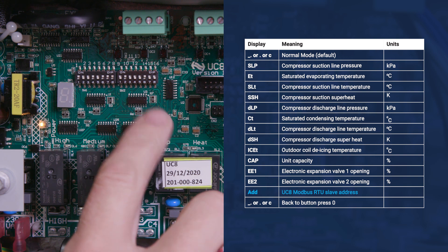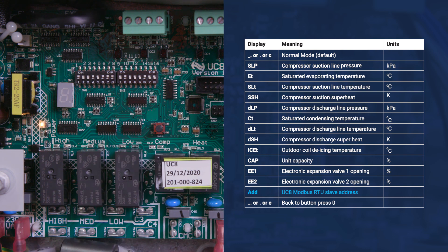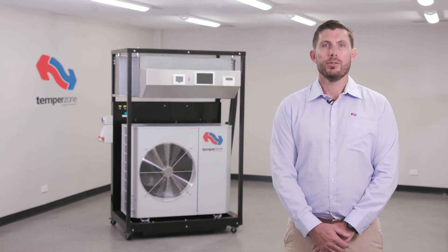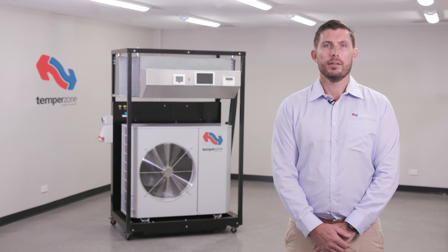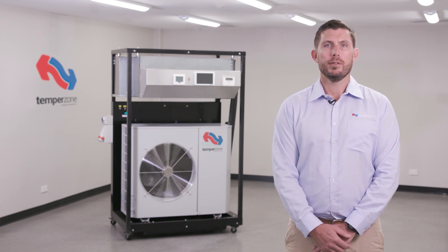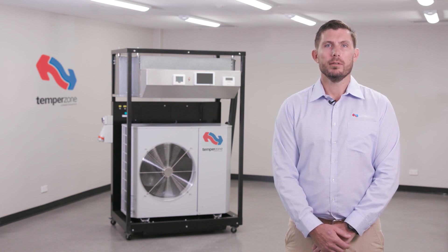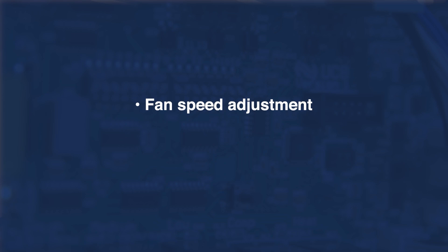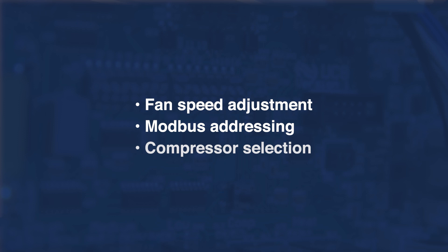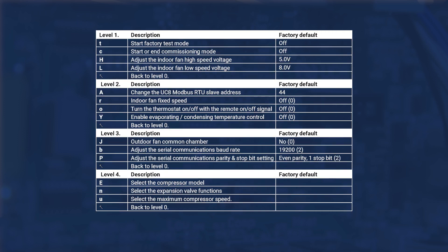The UC8 will return to normal operation after 15 seconds. The UC8 controller contains a menu of adjustable parameters available to technicians. Some of these include fan speed adjustment, modbus addressing, and compressor selection. Function of the special modes can be found in the UC8 operation manual.